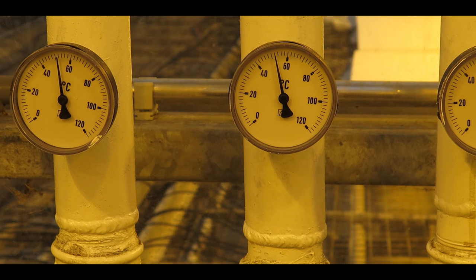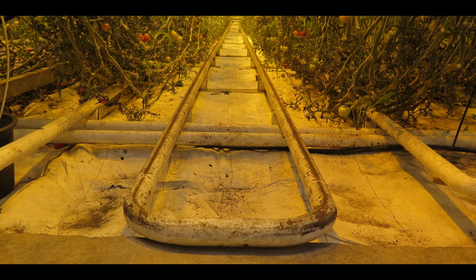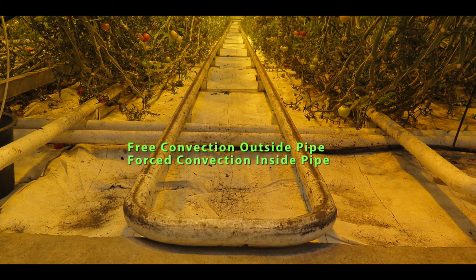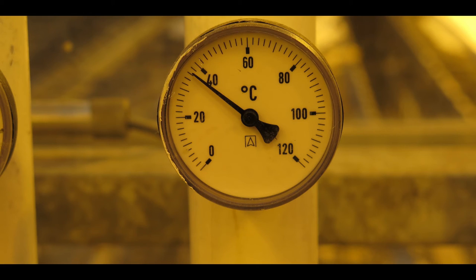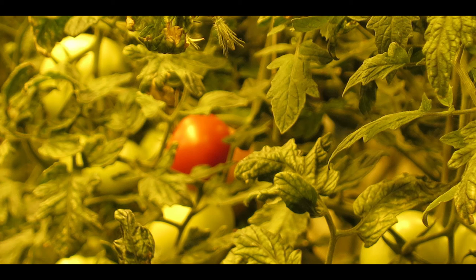The water comes in at about 52 degrees C. They then circulate it through these pipes on the bottom of the greenhouse for natural convection as well as providing the circulation mechanism. And then the water drops down to about 36 degrees C and they grow tomatoes with it. Really neat application of the geothermal heat.